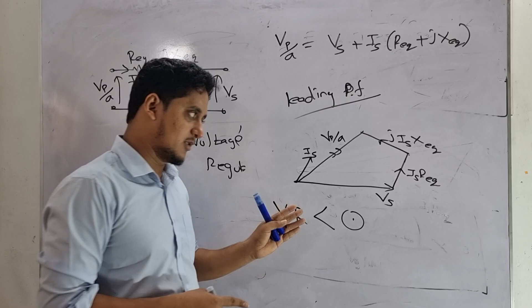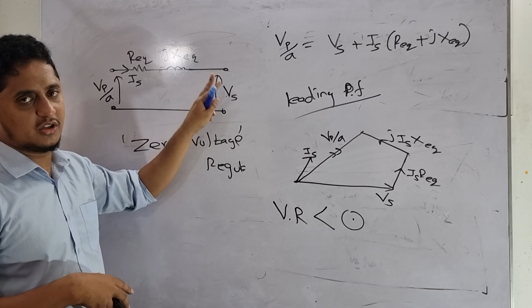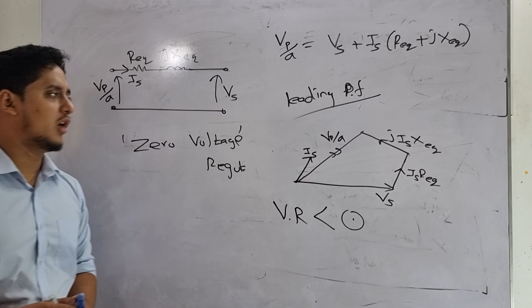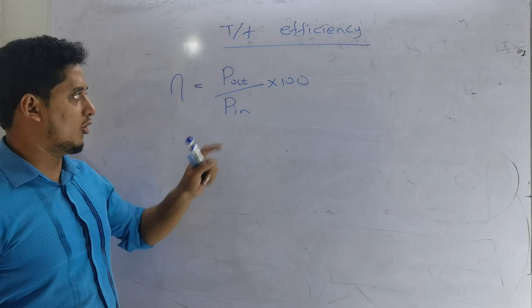When voltage regulation is greater than 0, the secondary side voltage decreases due to voltage drop. When voltage regulation is less than 0, the secondary voltage rises because of the capacitive load present in leading power factor. So normally in lagging power factor the voltage decreases, while in leading power factor the secondary voltage increases. I hope you now have a clear idea about leading, lagging, and zero voltage regulation.